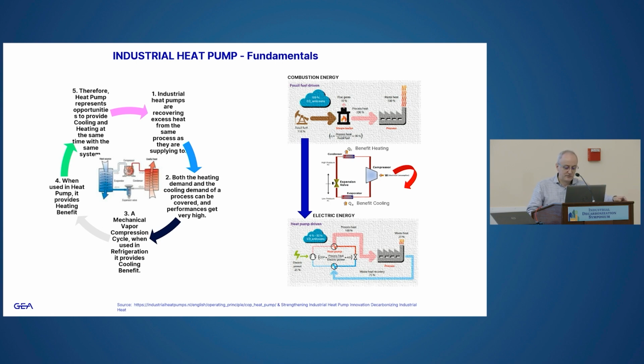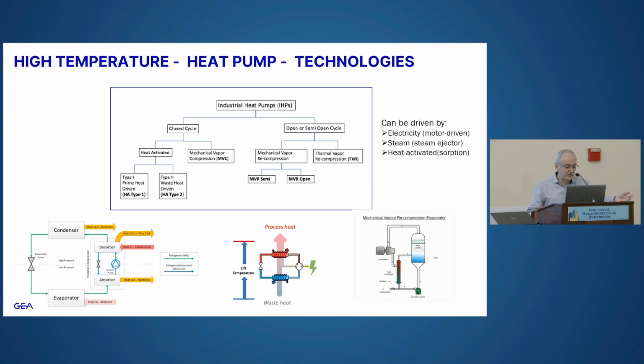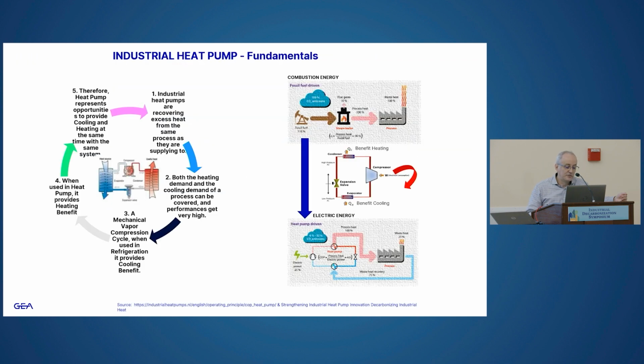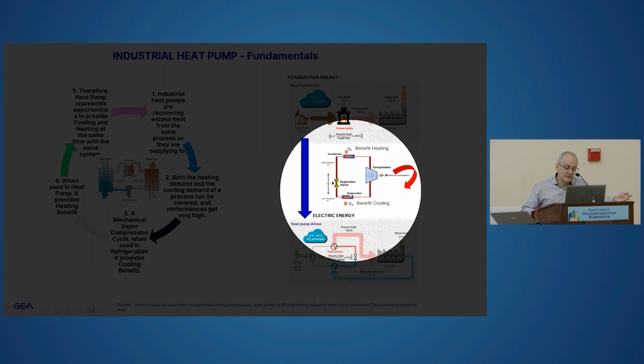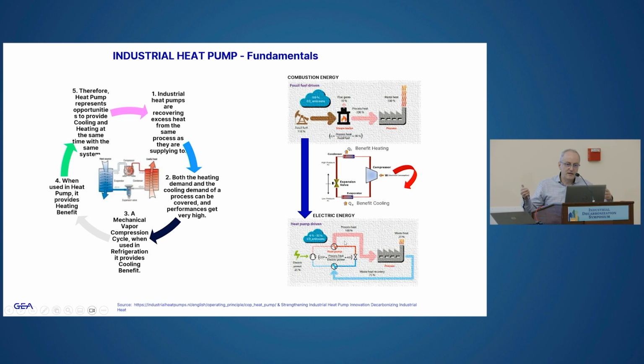Yeah, so going back to these technologies, basically you need a waste heat source to the heat pump, and it will raise it up in pressure and temperature depending on what technology you're using. So you know that it's basically competing against combustion energy. Now you turn that famous boiler into electrical heating. That's where the heat pump comes into the game, right? Basically you're combining the heat that happens from compressing a gas with the heat of the waste source. You add those two, and now you have more units of heat available and produce more heat than the combustion energy.